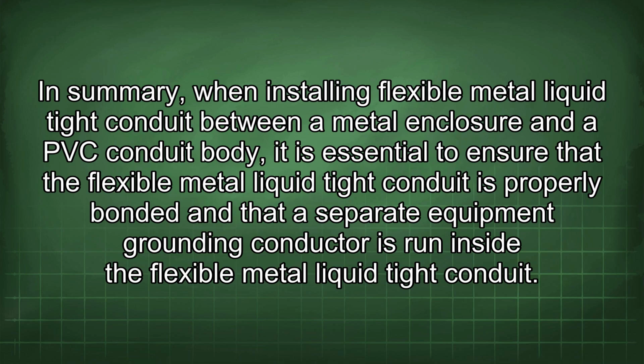In summary, when installing flexible metal liquid tight conduit between a metal enclosure and the PVC conduit body, it is essential to ensure that the flexible metal liquid tight conduit is properly bonded and that a separate equipment grounding conductor is run inside the flexible metal liquid tight conduit.